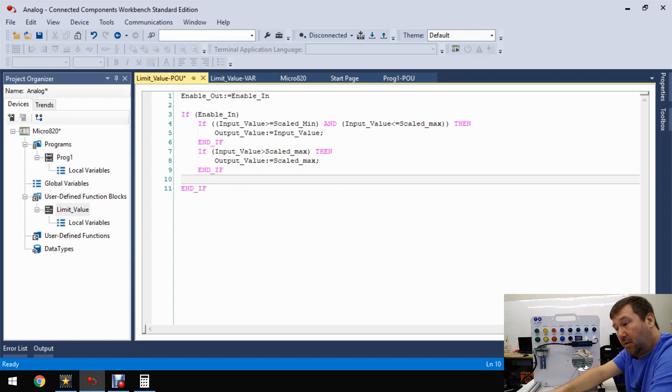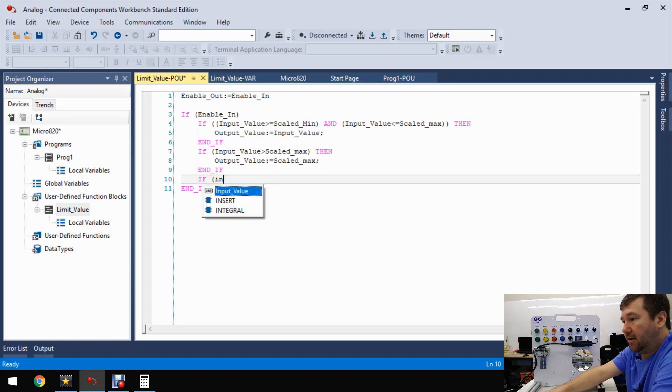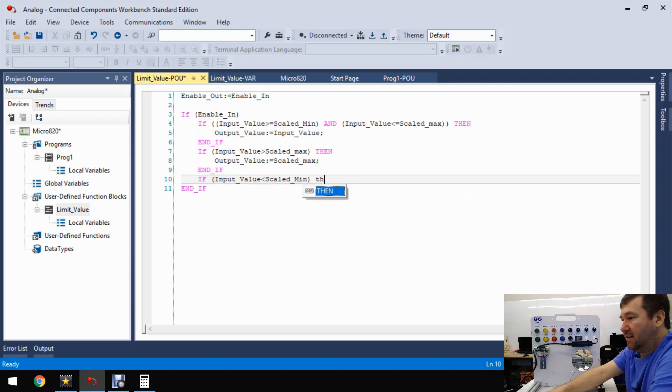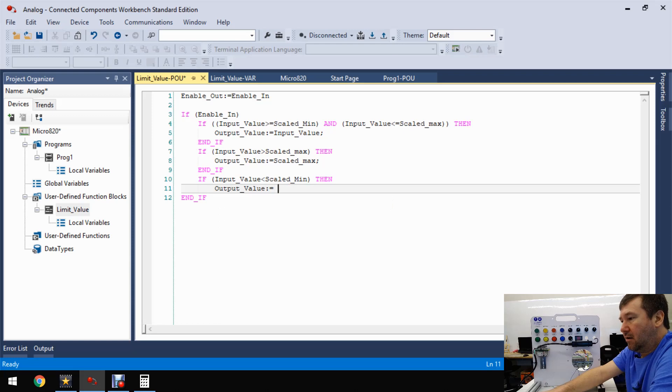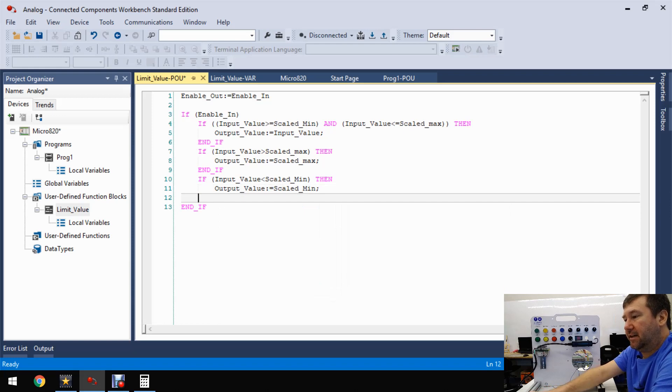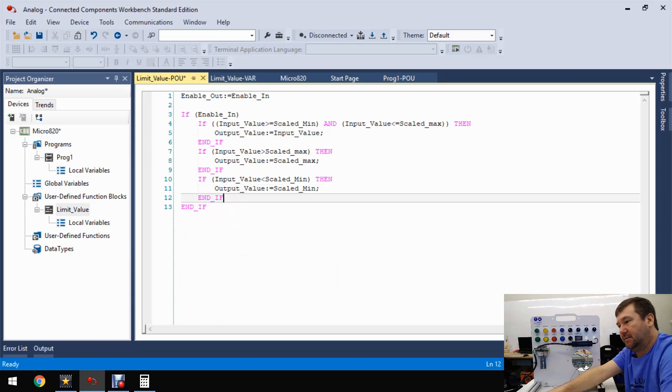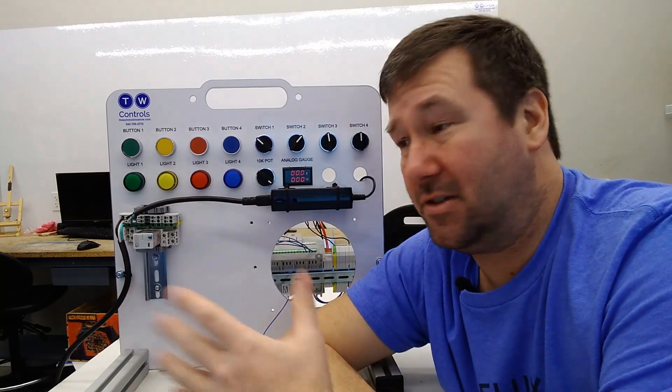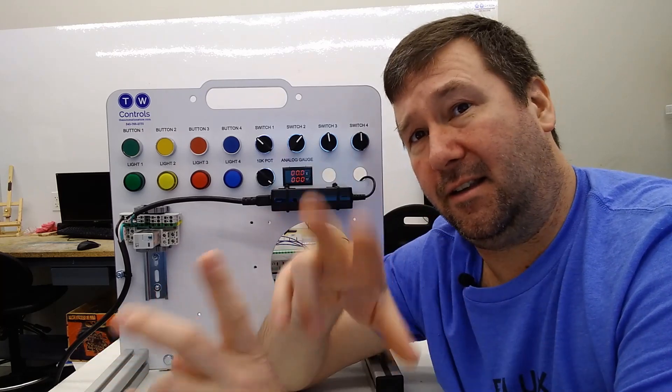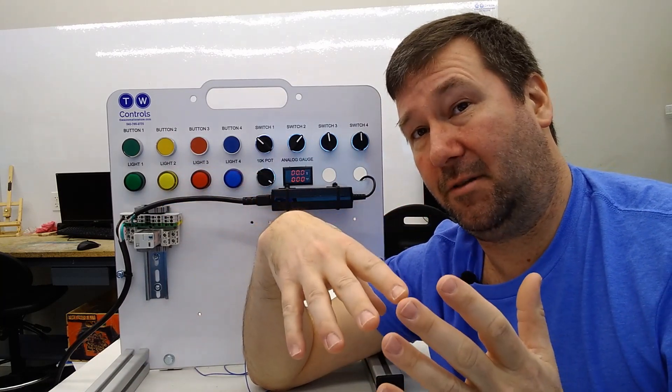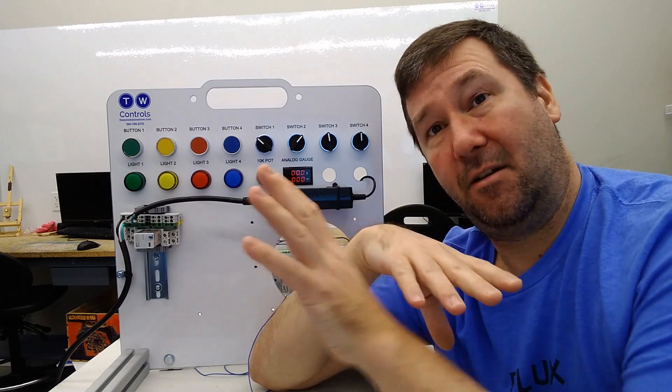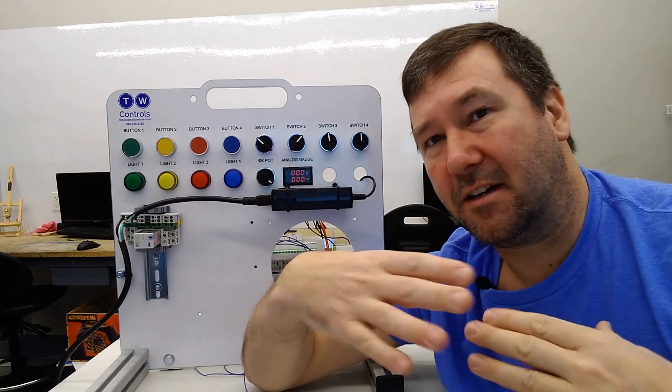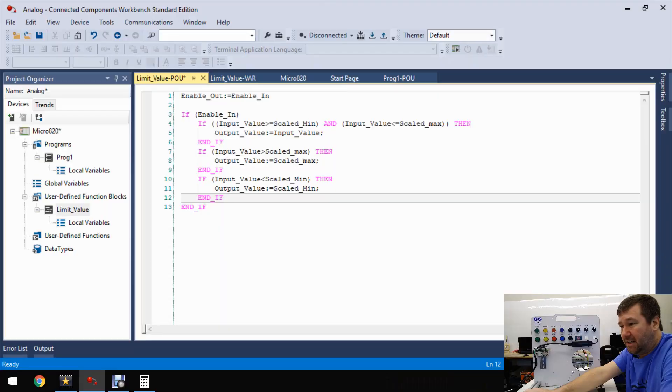So our output value will equal our input value. And then we put a colon to say an end of that line, and then we're also going to end this end if. So end if. Now that doesn't end our other end if. So now we're going to do another if-then. And then again, we're going to look at that input value. And if it is greater than our scaled max, then our output value is going to equal our scaled max. And put a semicolon. And then we're going to end that if. And then let's do one more for if it's too low. So if our input value is less than our scaled min, then our output value is going to equal our scaled min, semicolon, and then we'll end that if.